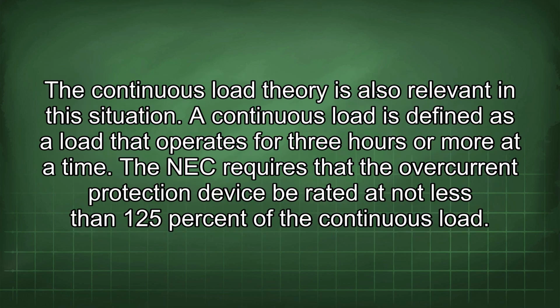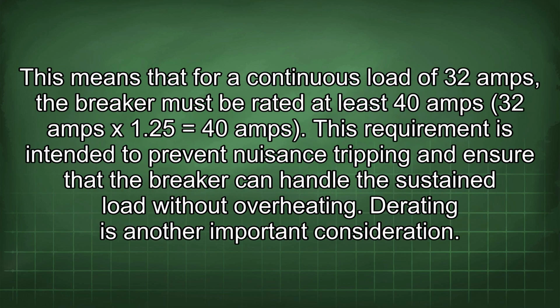The continuous load theory is also relevant in this situation. A continuous load is defined as a load that operates for 3 hours or more at a time. The NEC requires that the overcurrent protection device be rated at not less than 125% of the continuous load. This means that for a continuous load of 32 amps, the breaker must be rated at least 40 amps. 32 amps x 1.25 equals 40 amps. This requirement is intended to prevent nuisance tripping and ensure that the breaker can handle the sustained load without overheating.